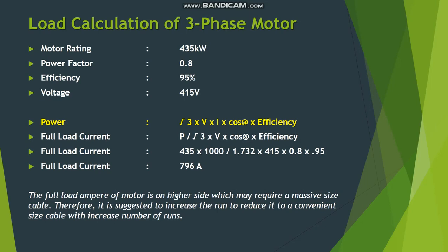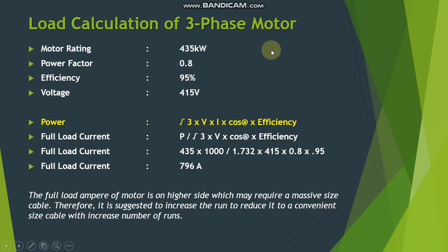Let's start. I would like to set an example for a motor with a capacity of 435 kilowatts, which is a three-phase motor with a power factor of 0.8. The efficiency of the motor is 95% and it will operate at 415 volts. The power formula for calculating motor rating is √3 × V × I × cos θ × efficiency. By rearranging this formula, you can calculate the full load current, which comes to 796 amperes.